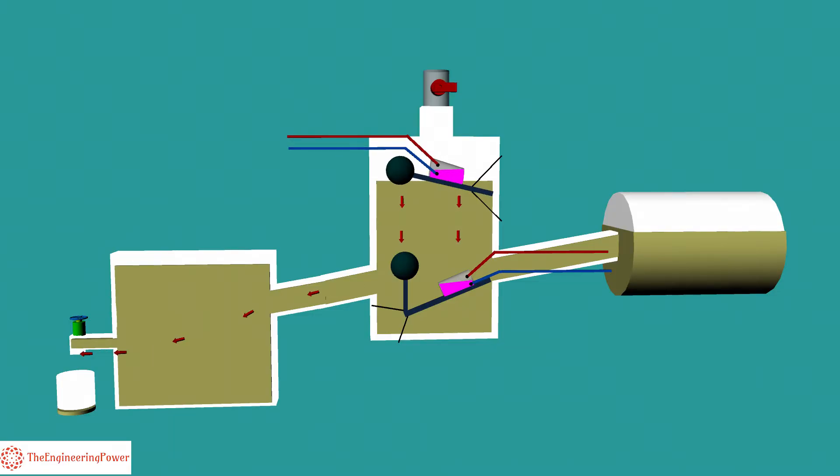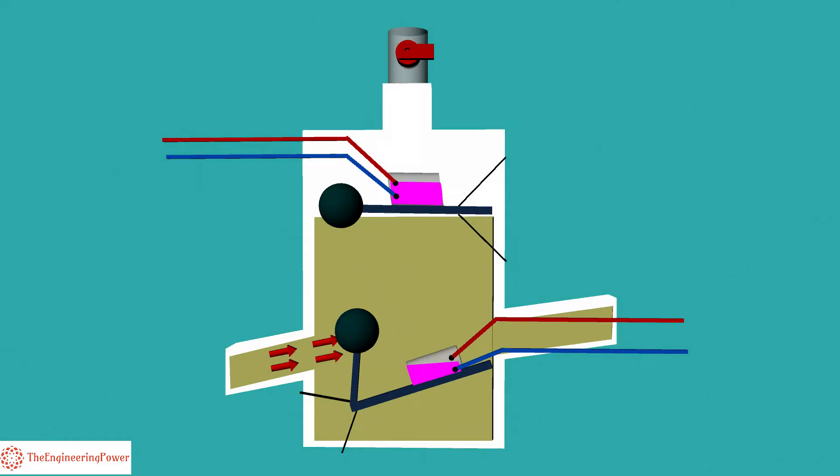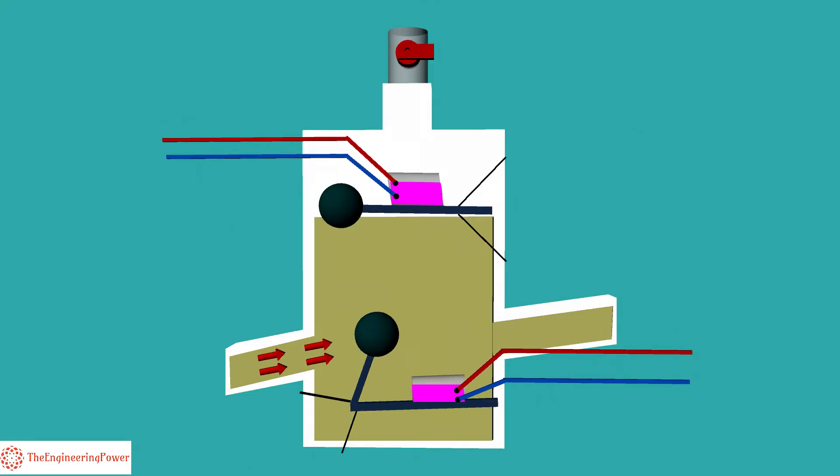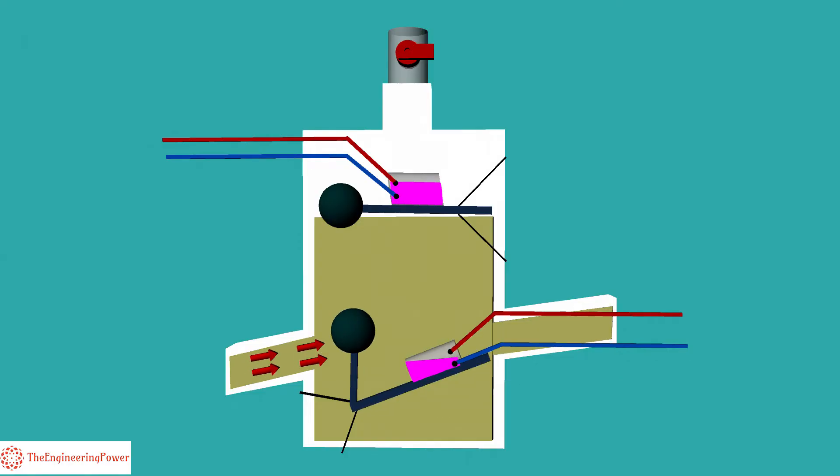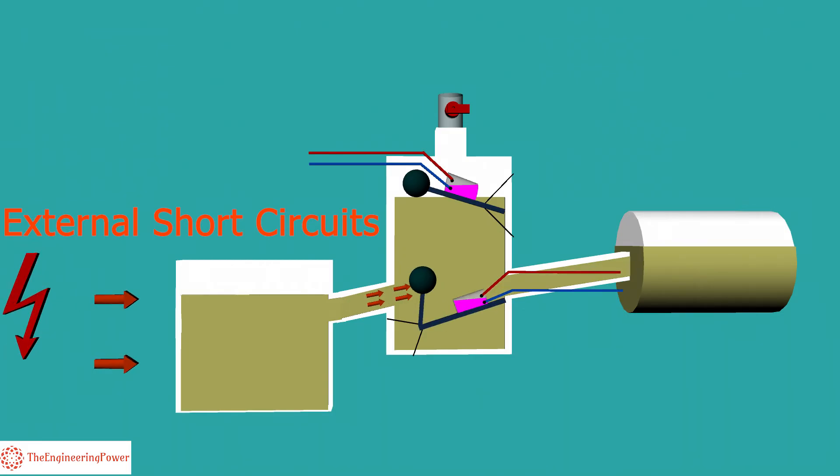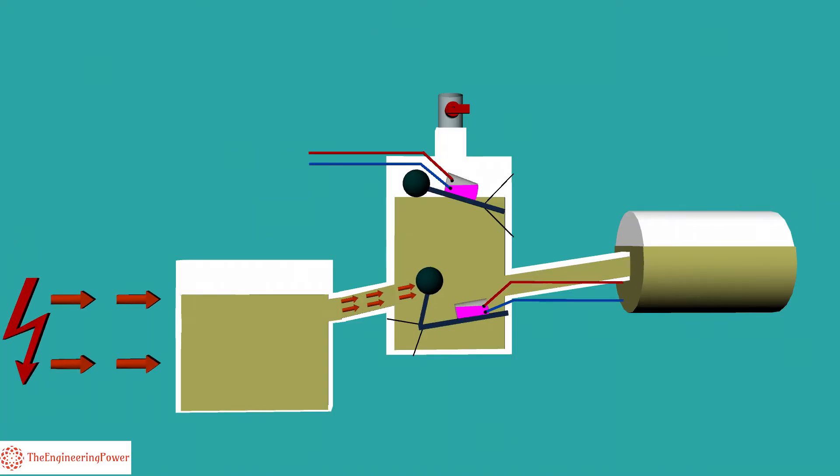Similarly, when taking oil sample from an energized transformer, the oil level can lower down resulting in false operation of the alarm circuit. Lower float can operate falsely resulting in tripping of the transformer if the oil velocity in the pipe is sufficient to trip over the float even if it's not due to internal fault. This can occur in case of external short circuits when high currents flowing through the winding cause overheating of the copper and oil and cause the oil to expand.